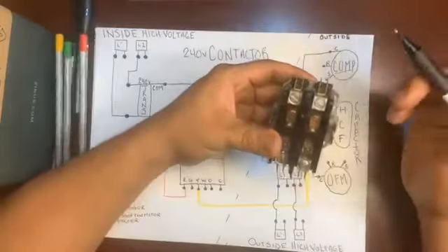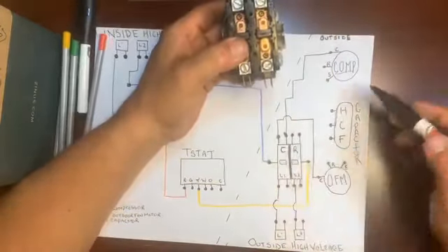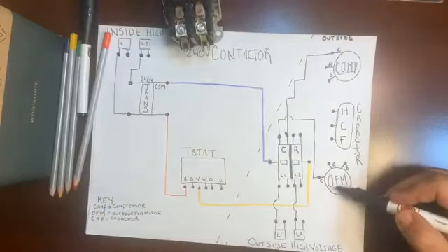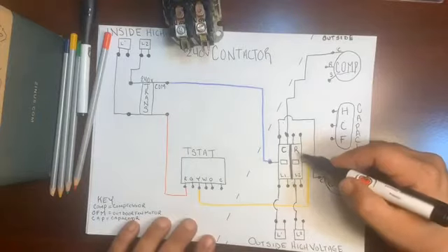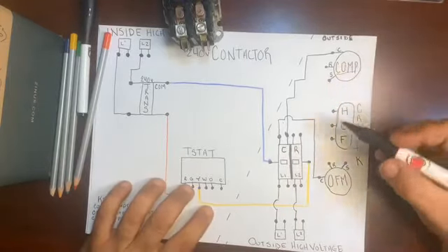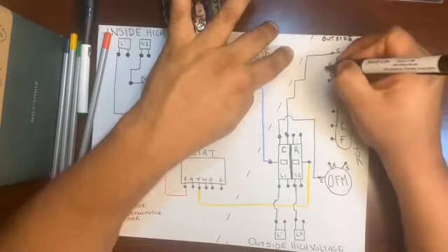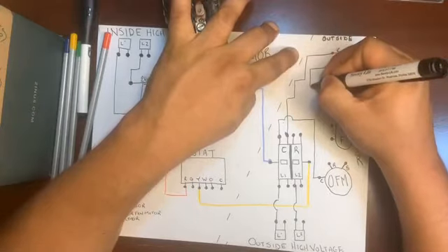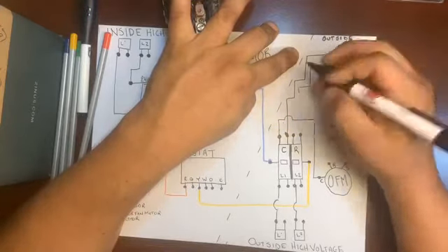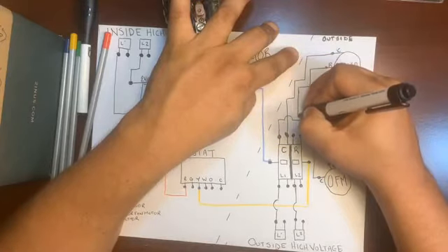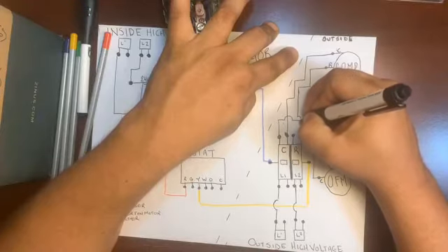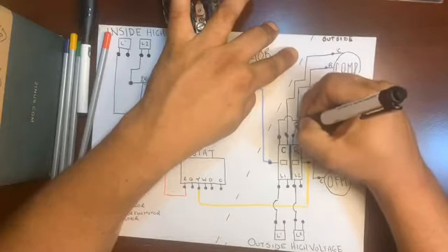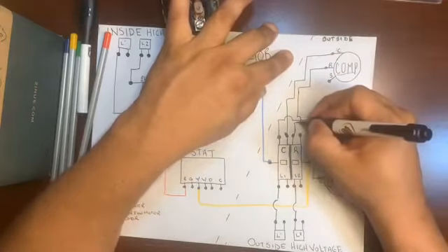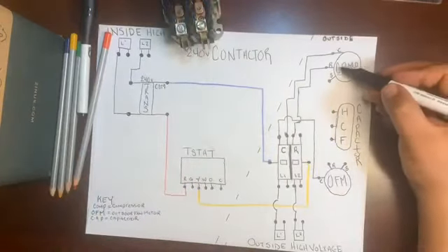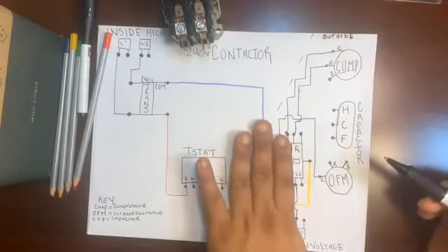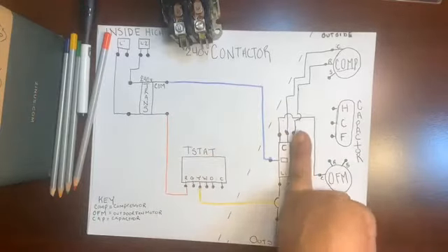So we've discussed and agreed that this is our common leg. We've brought common to the compressor, common to the outdoor fan motor. Now let's look at our run leg. Okay, now we have a run leg on the compressor, run leg on the outdoor fan motor. So we're going to run the run down pretty close to the other one, the common that's coming down. We're going to jump a bridge and bring it all the way down. So now we have connected the run leg from the compressor to the run side of the contactor. There's two sides, your run side and your common side.